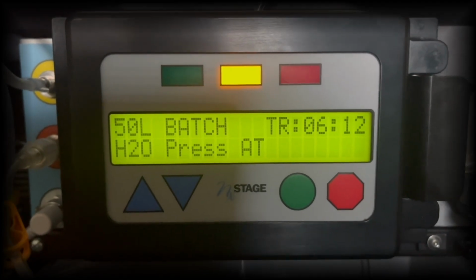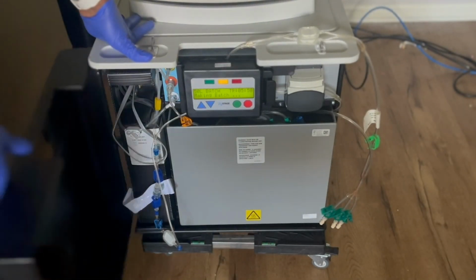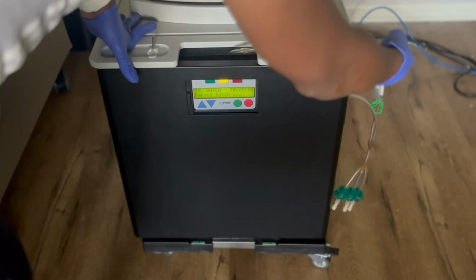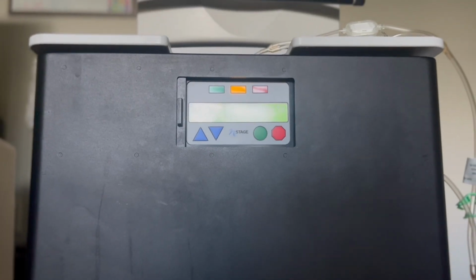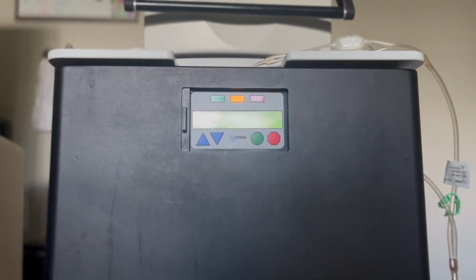The next thing you're going to do is press the green button, press go, and it's going to start testing. So after that, we are all done. You push it in, and I prefer to close the door. You don't have to close the door, but I prefer to close the door. It looks neat, and that's it. So for the next 6 hours, it's going to create a huge bag of dialysate, and then I'll be ready to use it for dialysis, which will be the next video we'll start making.